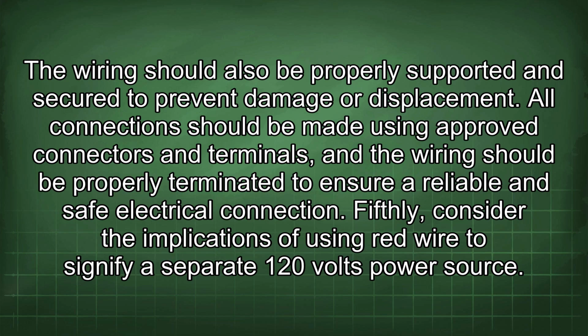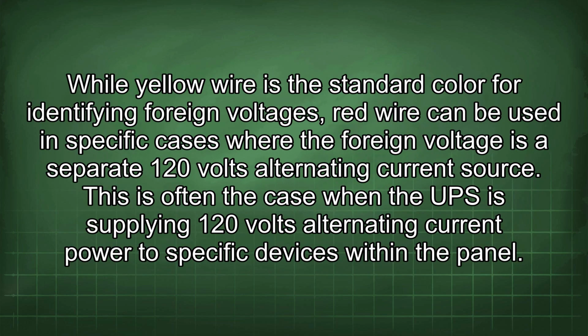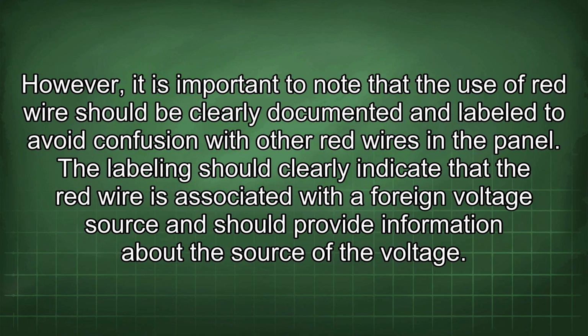Fifthly, consider the implications of using red wire to signify a separate 120 volts power source. While yellow wire is the standard color for identifying foreign voltages, red wire can be used in specific cases where the foreign voltage is a separate 120 volts alternating current source. This is often the case when the UPS is supplying 120 volts alternating current power to specific devices within the panel. However, it is important to note that the use of red wire should be clearly documented and labeled to avoid confusion with other red wires in the panel. The labeling should clearly indicate that the red wire is associated with a foreign voltage source and should provide information about the source of the voltage.